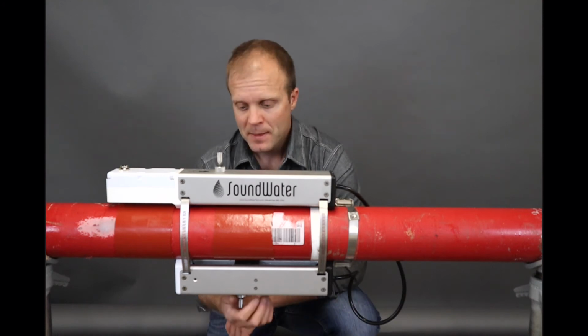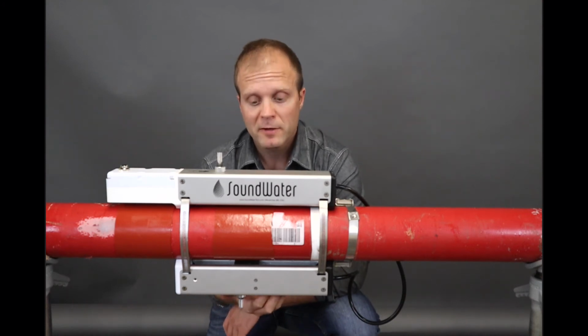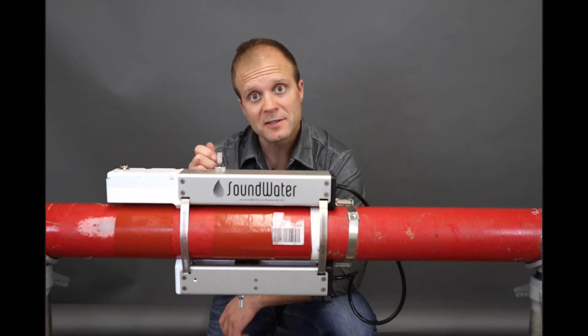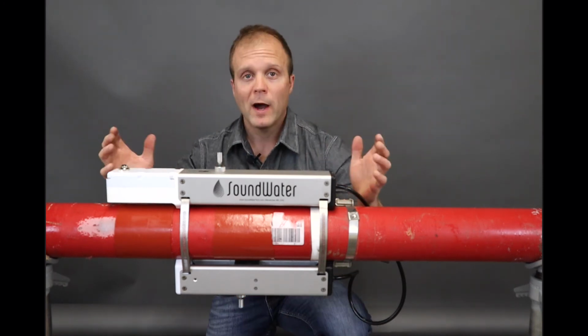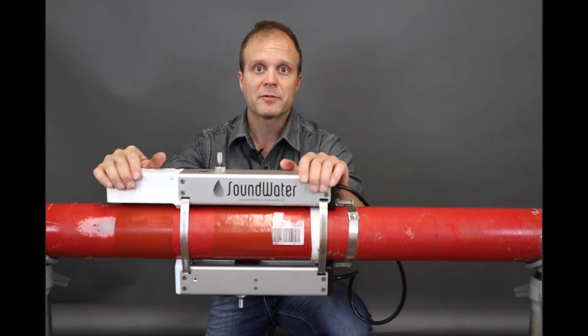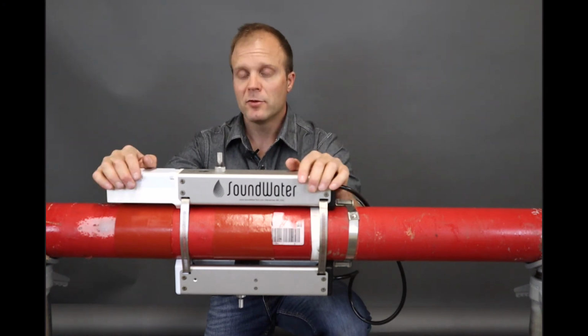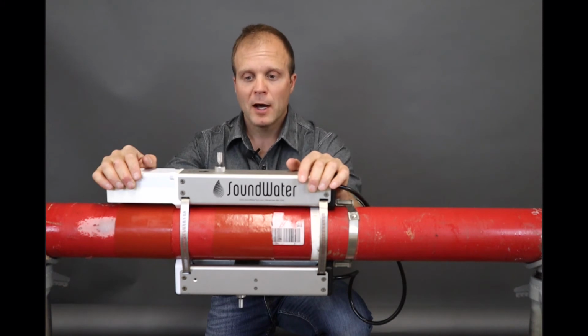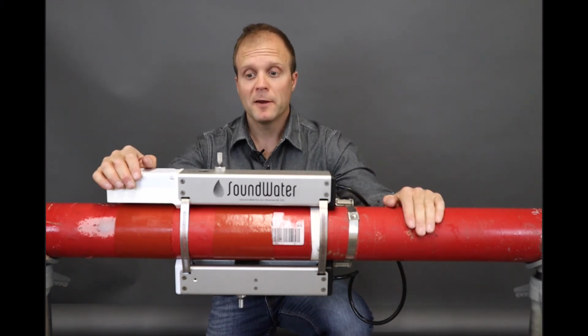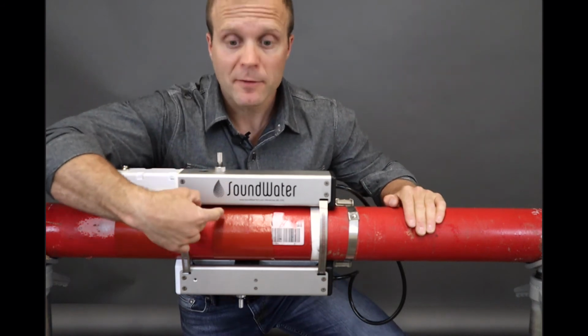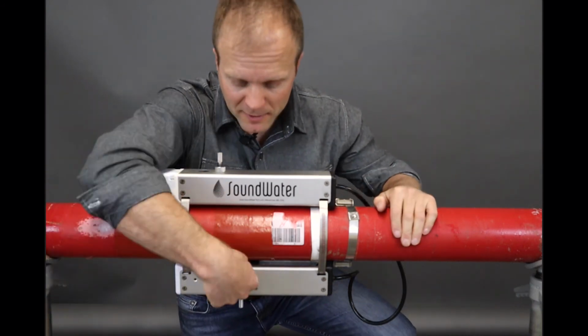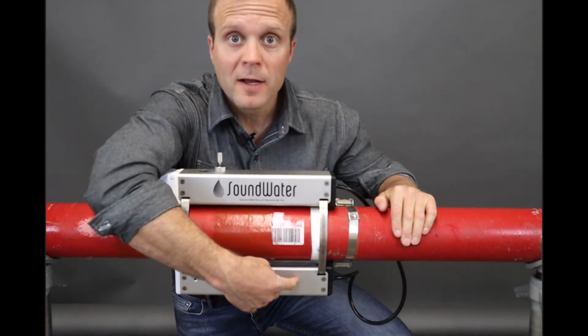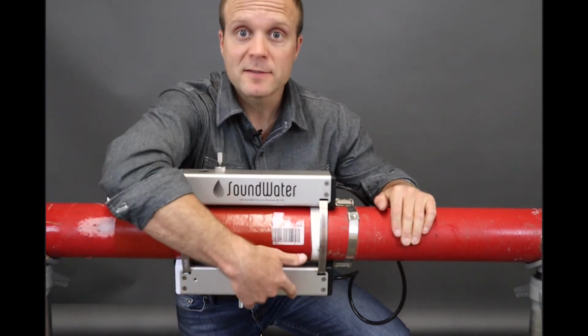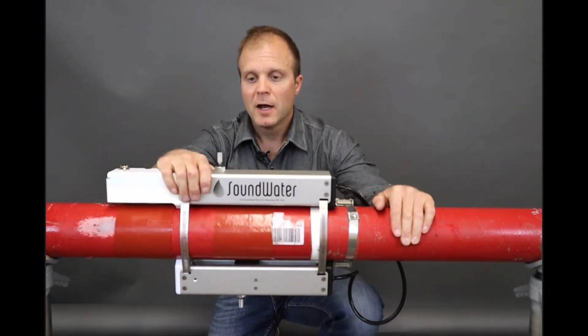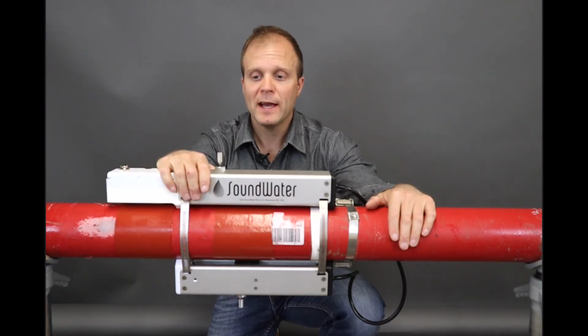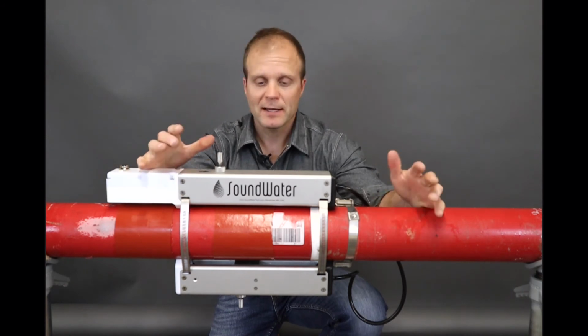So there's a ruler on the flow meter on the bottom half here, and we need to slide the transducer into the right spot. Why do we have to do that? Because this meter can be installed on pipes ranging from 2 inches up to 12. So we need to make sure, depending on what pipe we put it on, that the sound is going to transmit from one transducer through the pipe and hit the receiver. So if it's a bigger pipe, this receiver needs to be moved a little bit farther down so that it's at the spot where the sound is coming out across the pipe. It's easy to do. The app that we have to set up the flow meter will tell us exactly what to do.